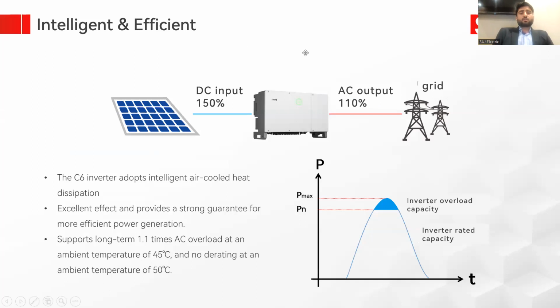Intelligent and efficient working of the C6 series. DC input is 150% and AC output is 110%. If your inverter is 100 kilowatt, it will deliver 110 kilowatt. The C6 inverter adopts intelligent air-cooled heat dissipation, with an excellent effect, providing a strong guarantee for more efficient power generation. Long-term 1.1 times AC overload at an ambient temperature of 45 degrees Celsius, and no derating at an ambient temperature of 50 degrees Celsius.